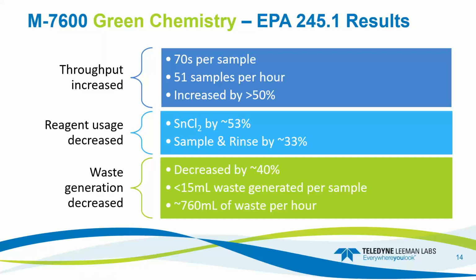So this method was optimized for throughput and productivity, with a total analysis time of 70 seconds per sample. At this rate, 51 samples could be analyzed in an hour, and that increases the throughput by more than 50% compared to the normal range method that we saw the peak profile for previously. When comparing the green chemistry to the standard methods and tubing setup, stannous chloride reagent consumption is reduced by 53%, and sample and rinse by 33%. Our waste generation is also decreased by about 40%. For this analysis, the samples generated less than 15 milliliters of waste per sample, or about 760 milliliters of waste per hour.